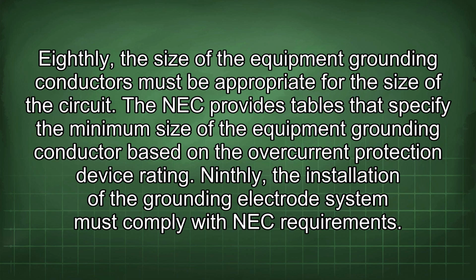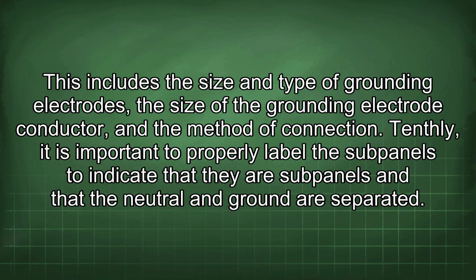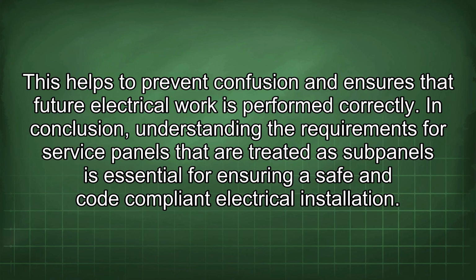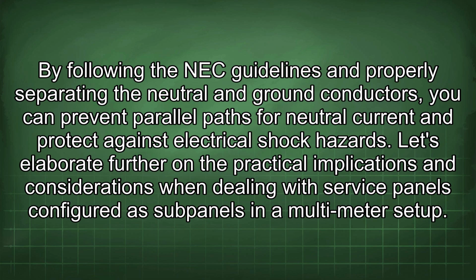Ninthly, the installation of the grounding electrode system must comply with NEC requirements. This includes the size and type of grounding electrodes, the size of the grounding electrode conductor, and the method of connection. Tenthly, it is important to properly label the subpanels to indicate that they are subpanels and that the neutral and ground are separated. This helps to prevent confusion and ensures that future electrical work is performed correctly. In conclusion, understanding the requirements for service panels that are treated as subpanels is essential for ensuring a safe and code-compliant electrical installation. By following the NEC guidelines and properly separating the neutral and ground conductors, you can prevent parallel paths for neutral current and protect against electrical shock hazards.